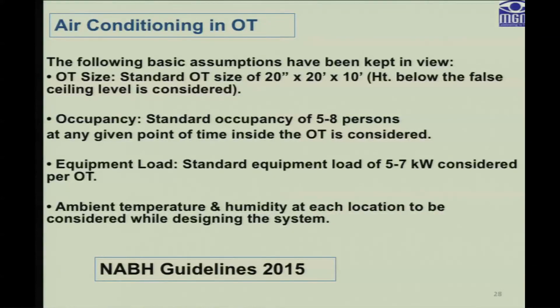NABH guidelines state that the standard OT size should be 20 by 20 by 10 feet. The occupancy should be 5 to 8 persons at any given point. Equipment load should be considered as 5 to 7 kW per OT, along with standards for ambient temperature and humidity, which you can find in the NABH guidelines.